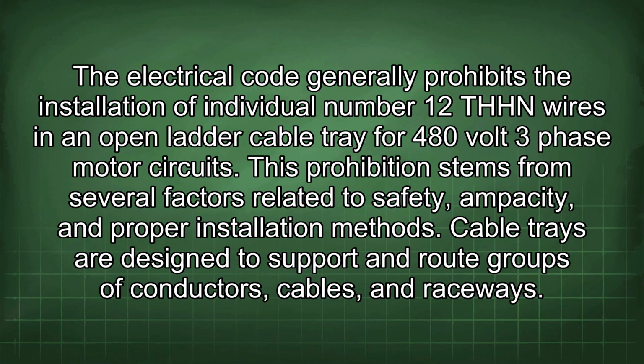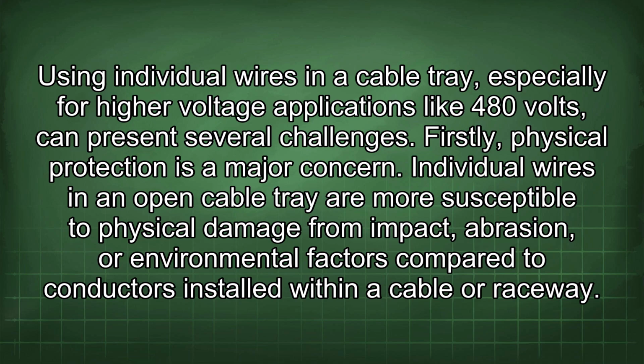The electrical code generally prohibits the installation of individual number 12 THHN wires in an open ladder cable tray for 480-volt three-phase motor circuits. This prohibition stems from several factors related to safety, ampacity, and proper installation methods. Cable trays are designed to support and route groups of conductors, cables, and raceways. Using individual wires in a cable tray, especially for higher voltage applications like 480 volts, can present several challenges.